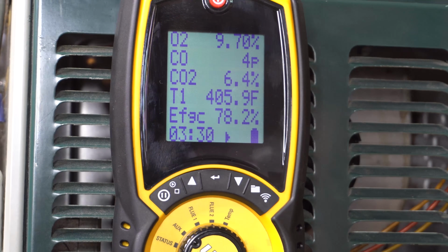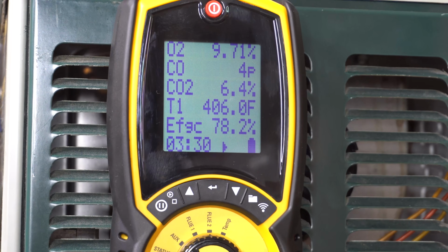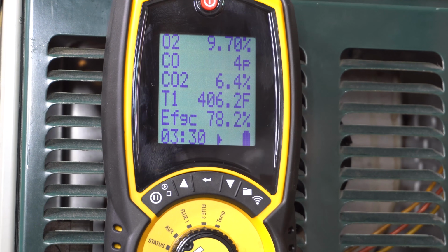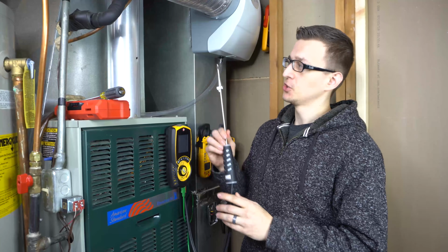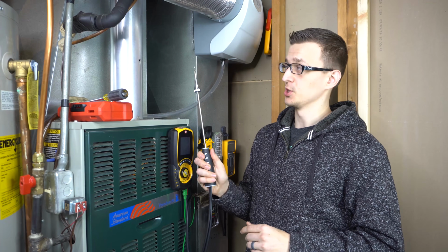So from these two readings that I got on my low stage and my high stage, I can safely say that my furnace is burning cleanly and it's running safely. And that is how one would go about checking the carbon monoxide levels in the furnace flue.